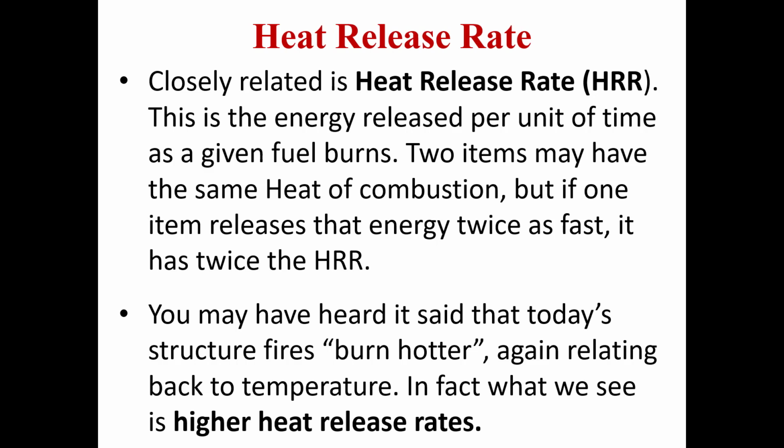A closely related concept is heat release rate. This is the energy released per unit of time as a fuel burns. Two items may have the same heat of combustion. They may have the same number of joules that would be released when they burn. But if that item releases that energy twice as fast, it has twice the heat release rate.